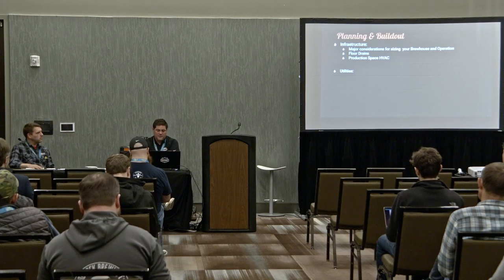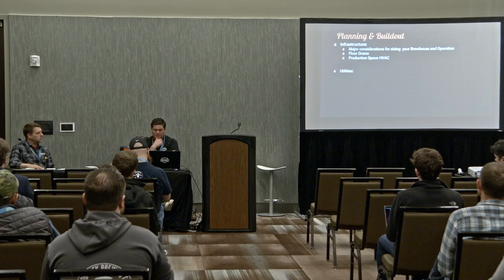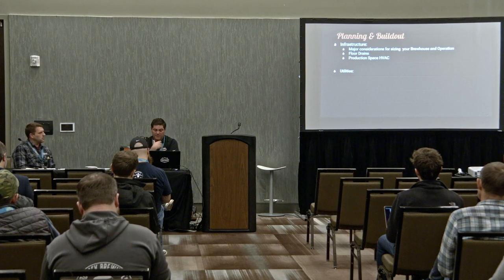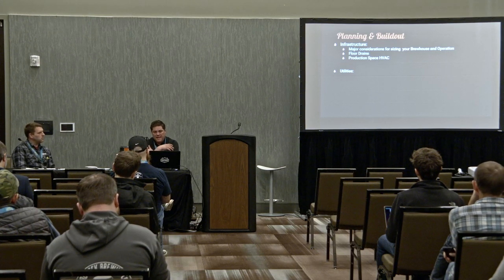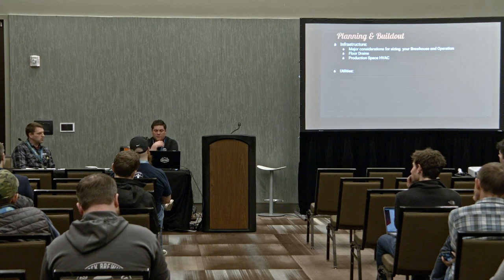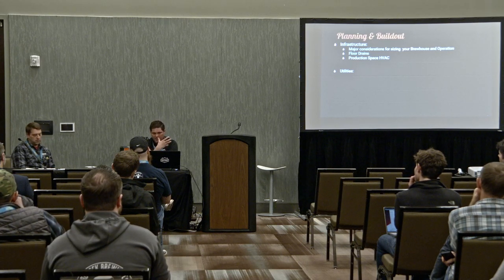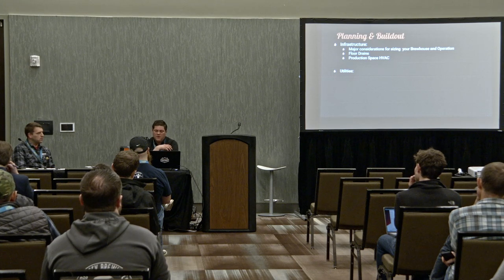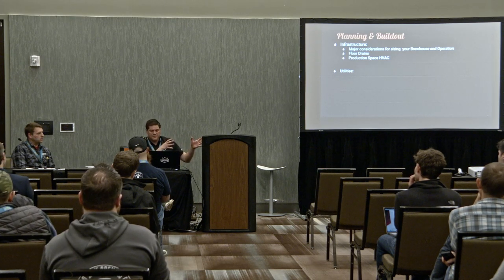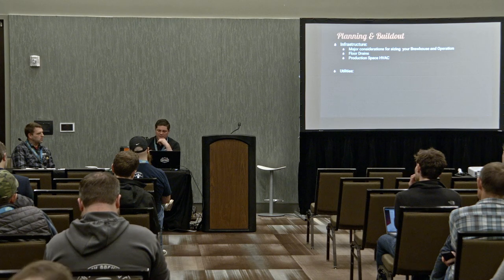One thing that we've seen a lot of is that it's not just about circulating air, like buying a big fan. Because of labor laws and certain things, the production space has to be heated and cooled in certain parts of the country, and I've seen that a lot in North Carolina. So production space HVAC, when you have 20 or 30 foot ceilings in some of these places, is a big consideration. You have a lot of steam coming off your equipment, and you're cleaning a lot with hot water. So think about where your production area is in the higher roof part of the building and your cellar is not, so you don't have to condition the entire space.